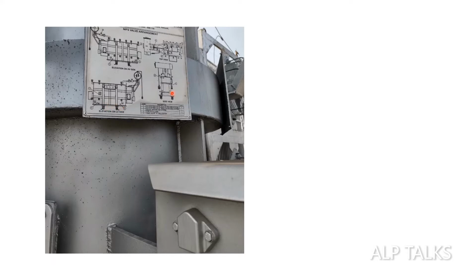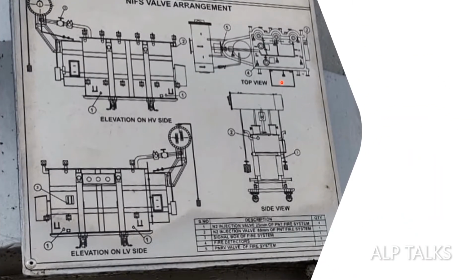Whenever we have a NIFS valve system, we should show it clearly. Otherwise, this is a clear view. We can observe here that we have two valves on one side and two valves on the other side. Generally they take a 25 mm valve. At the top also we have one valve, number 2 here, which is an 80 mm valve. Signal box, fire detection sensors, everything will be on the top cover. Generally the arc sensors will detect whatever fire is there.